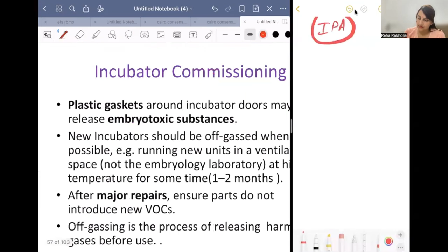The plastic gasket in an incubator contains embryotoxic substances, so we have to off-gas it first. We have to run the incubator for months before using it in the laboratory. New incubators should be off-gassed whenever possible. Off-gassing means running new units to remove the harmful gases in a ventilated space, not the indoor lab, at a high temperature for some time, like 1 to 2 months.